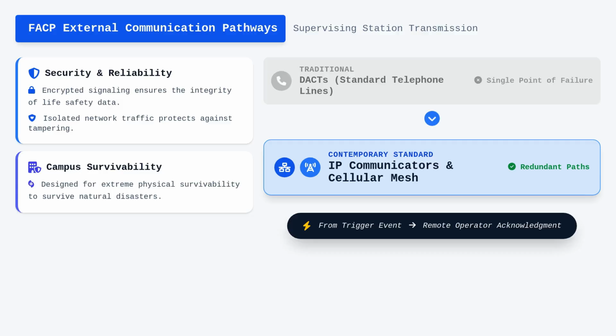For proprietary supervising stations that monitor massive distributed campus environments, the requirements extend to stringent physical survivability and cybersecurity protocols to protect against both intentional tampering and natural disaster damage. By isolating the internal network traffic and using encrypted signaling, these systems ensure that the integrity of the life safety information is maintained from the moment a trigger occurs at the device level until the alarm signal is acknowledged by a remote operator.